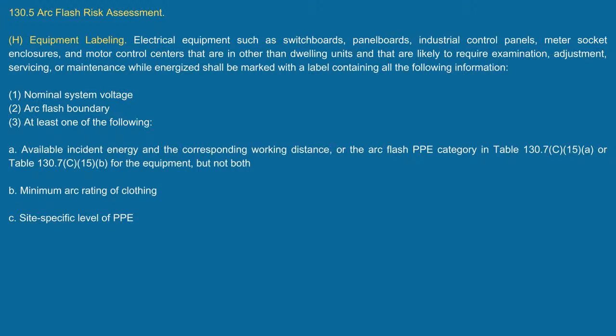I've never seen that, but what I have seen, when they want to put additional information, they may come in and put like the restricted approach boundary, the limited approach boundary as extra information that's on there. They also will put what the working clearance is to be around that equipment to make sure that they're meeting what the code says. For example, I've seen it where we're working on a UPS and there were 2 power sources. So you know that this equipment's fed by 2 power sources. So to establish an electrically safe work condition, you have to isolate both power sources. You can't just isolate one power source and dive in there. That's kind of what I was meaning by that.